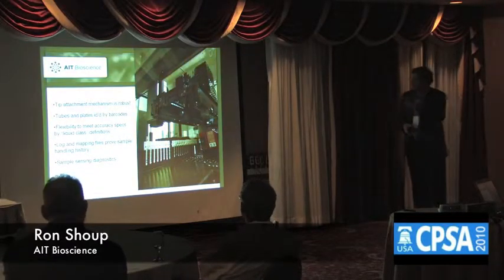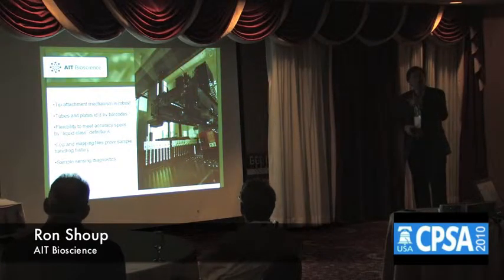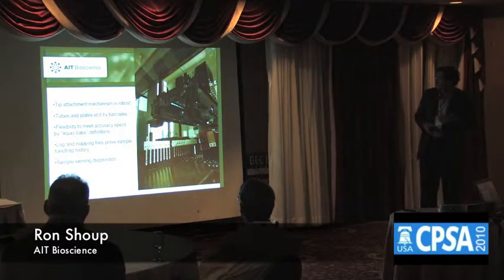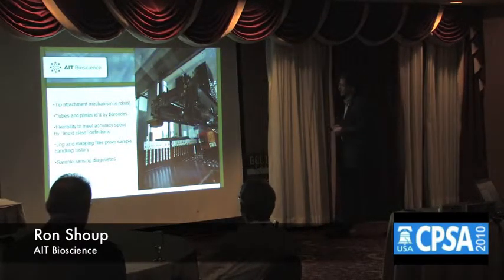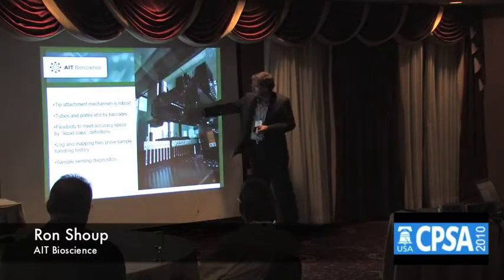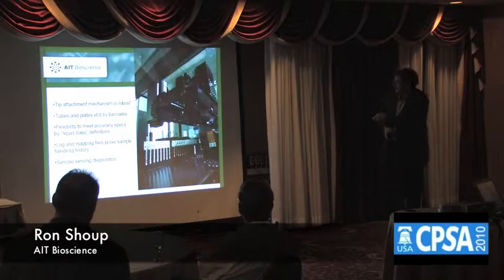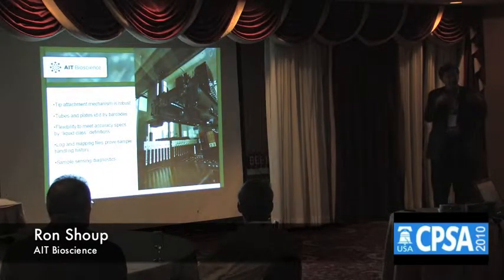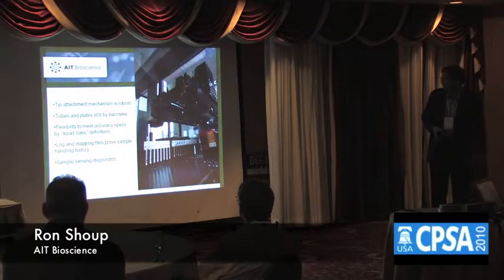When we started looking at that, we looked at how we could automate it. We picked the STAR system. A lot of pharma companies have the STAR system from Hamilton — I don't have any Hamilton stock, but the thing works extremely well. We have a deck with 12 pipetters and a 96-head. The samples sitting on the deck can all be read, so you have ultimate tracking of the entire process, from samples coming in through Watson to samples getting aliquoted to plates.